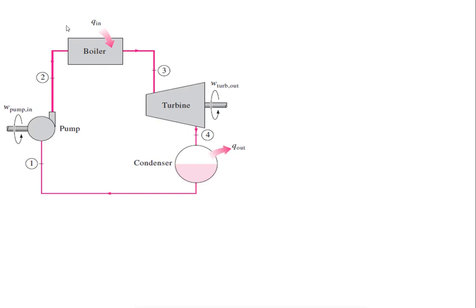Strictly speaking, the boiler consists of three components: the economizer, the evaporator, and the superheater. The economizer heats the subcooled water into saturated liquid. In the evaporator, it converts saturated liquid into saturated vapor. And in the superheater, it converts dry saturated steam into superheated steam. So the boiler consists of these three individual components, along with the steam turbine and condenser.